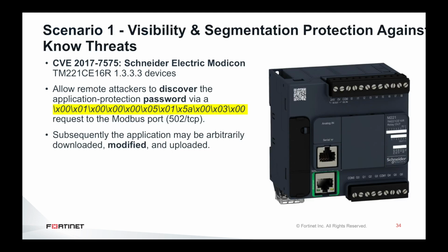known threats. Schneider Electric Modicon M221 running firmware 1.3.3.3 has a known CVE reported against it. So if the attackers were to run this string of characters, they will be able to discover the password, and with that they can modify the PLC task, causing disruptions and safety related issues.